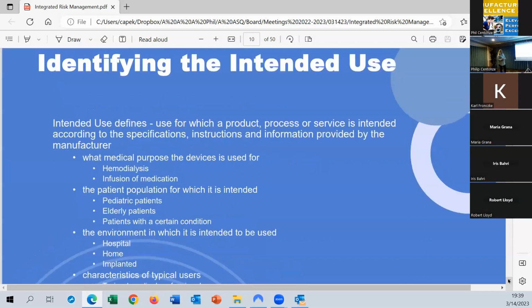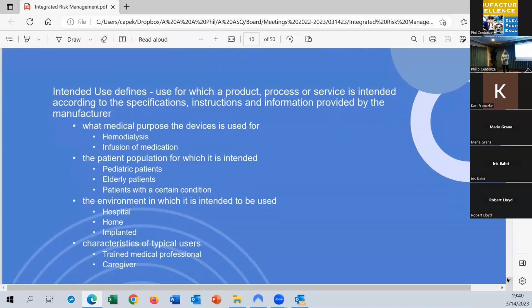So the first thing with medical devices that you have to do is identify the intended use, in order to determine what inherent risks exist for this intended use. For example, the risk for a hemodialysis device as opposed to an infusion pump will be different. So I need to know the intended use of my device. Who is intended to use this device? If it's going to be used on pediatric patients, the severity of some of the risks might be a lot higher than if it's going to be used on, I guess, normal healthcare patients. But you have to determine who the device is going to be used for.